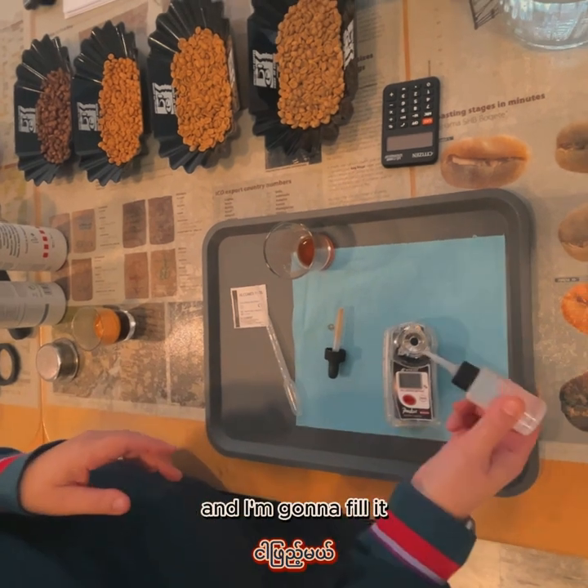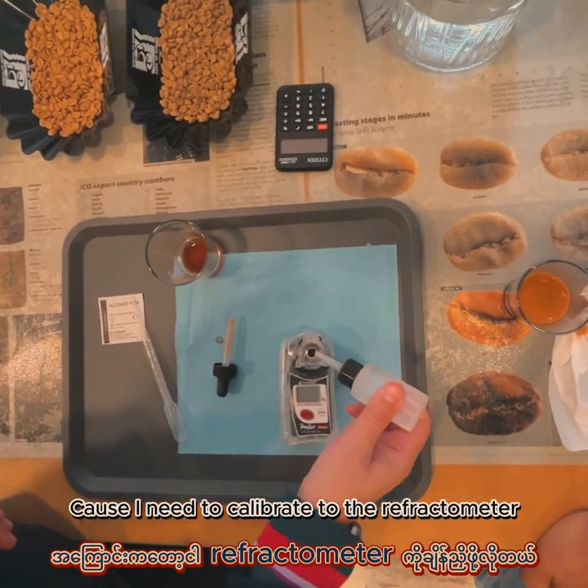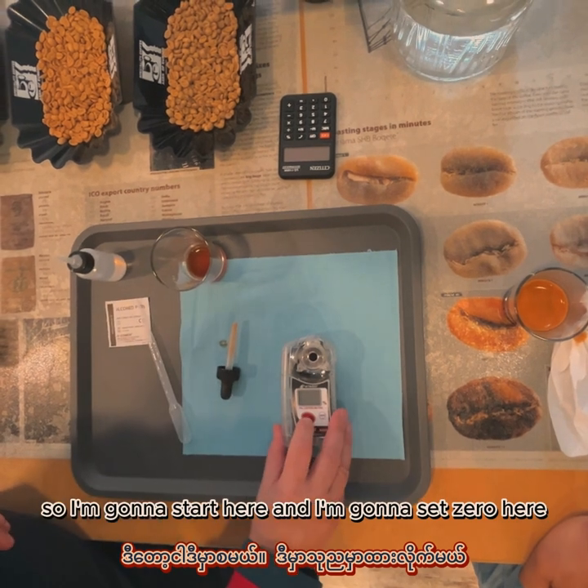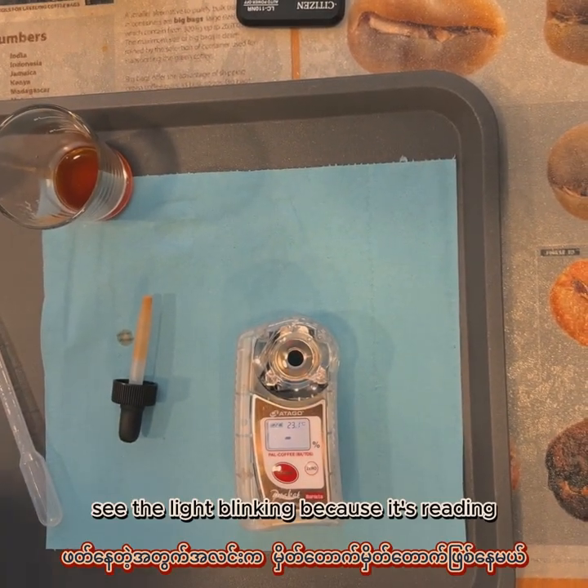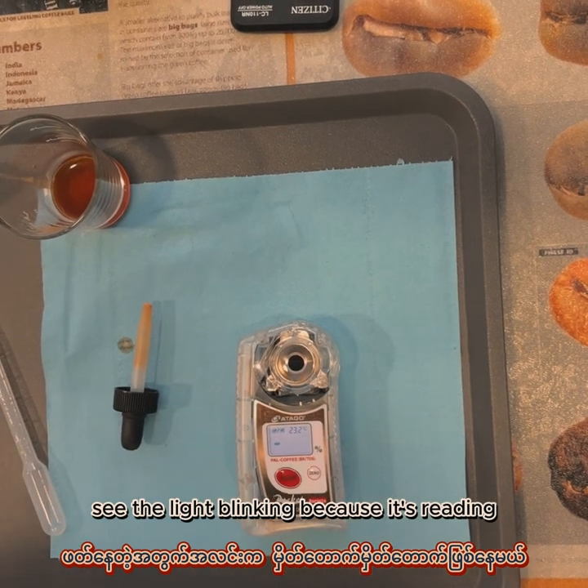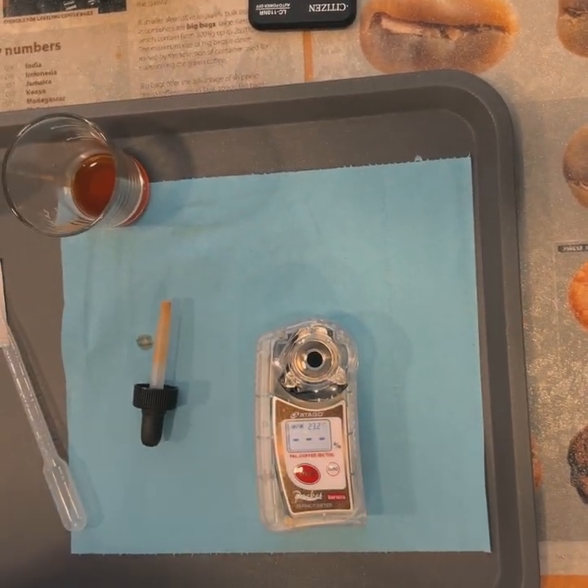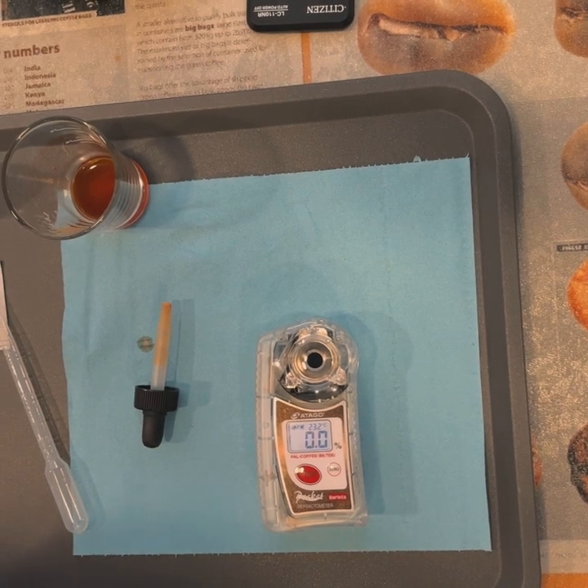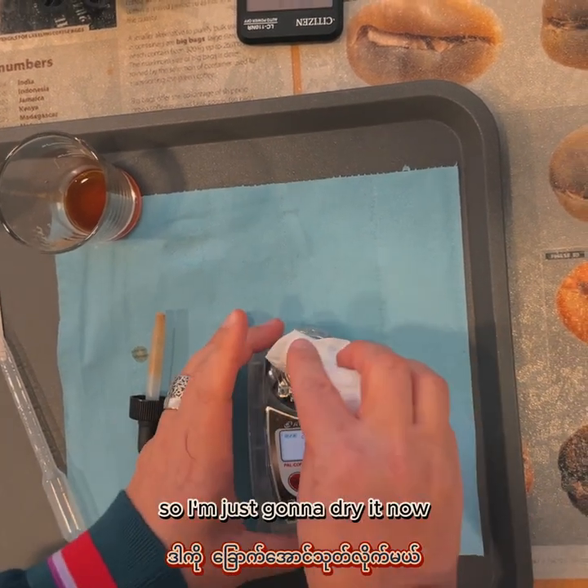This is distilled water and I'm going to fill it because I need to calibrate the refractometer. I'm going to start here and set zero here. You can see the light blinking. So 0.00 — it's calibrated. Now I'm just going to dry it.